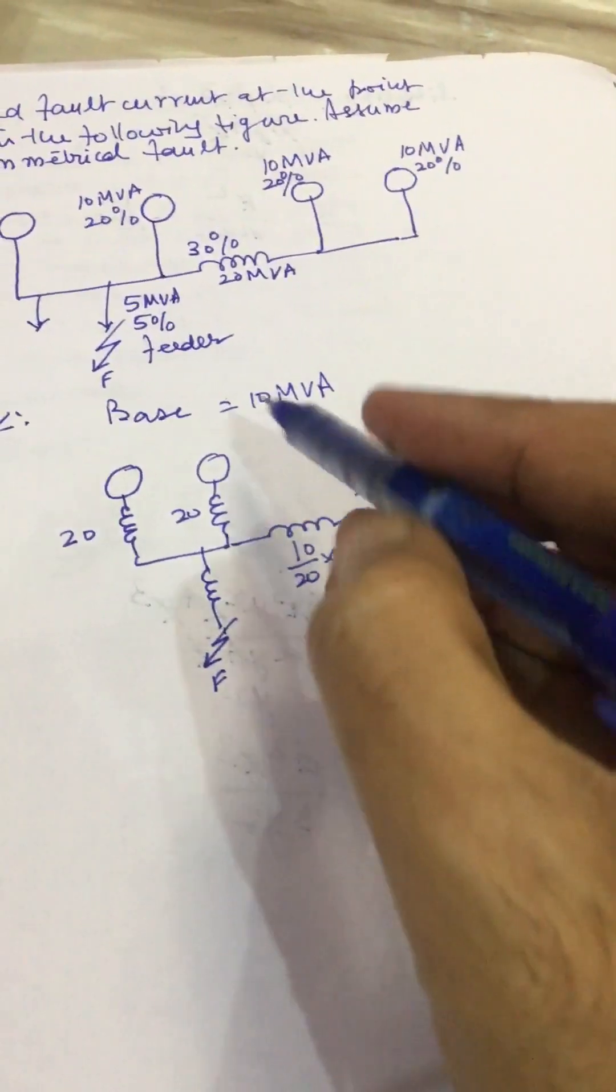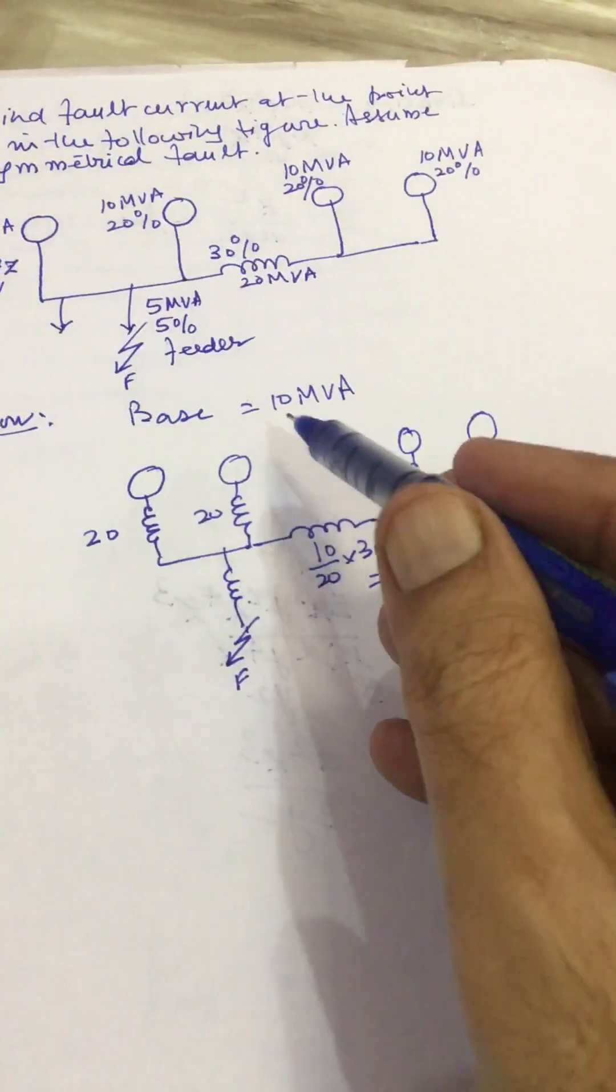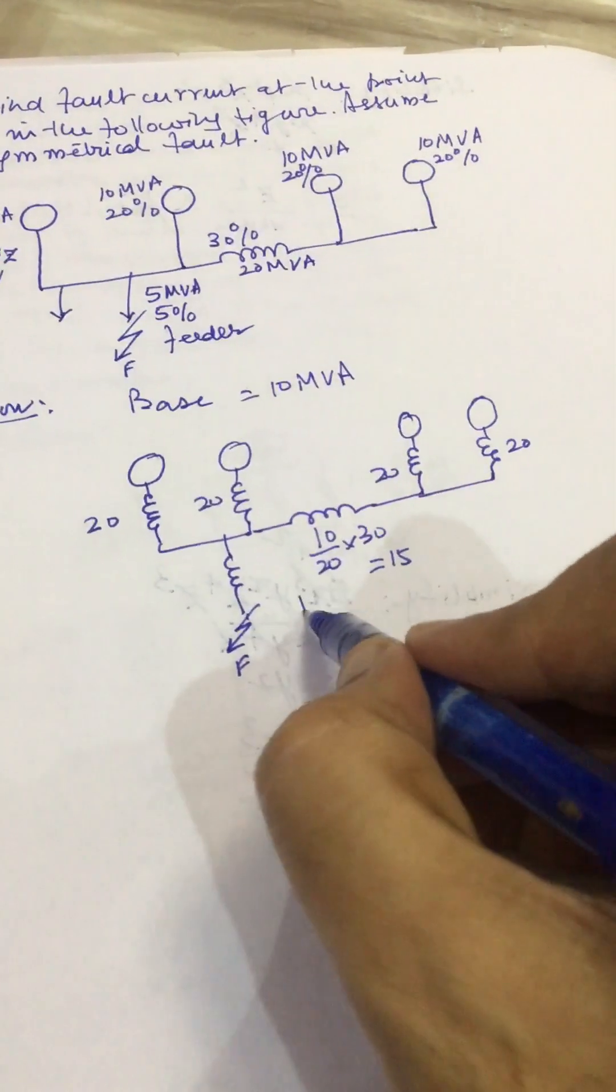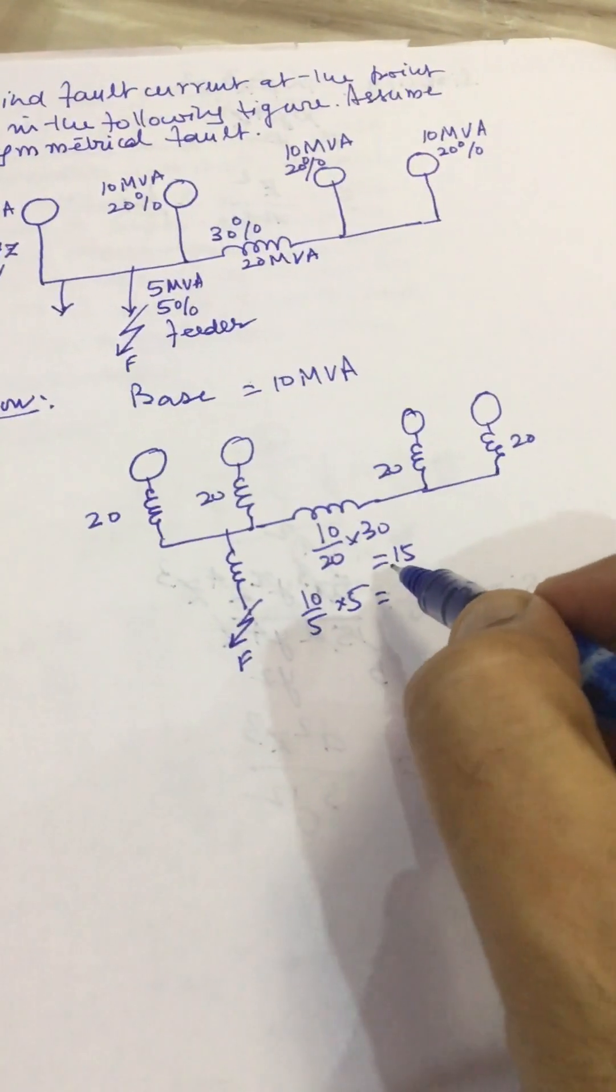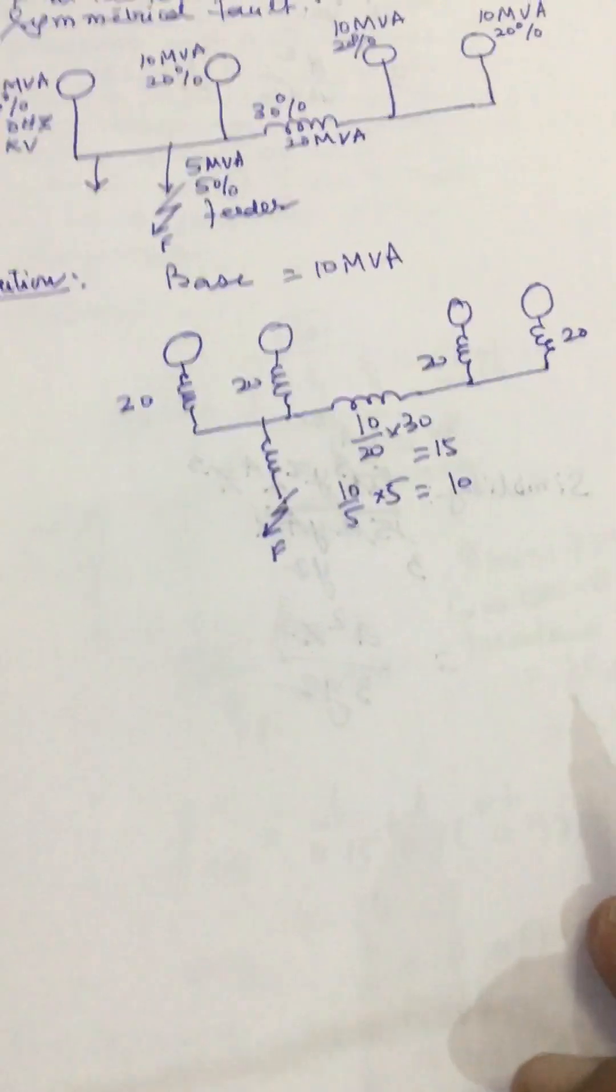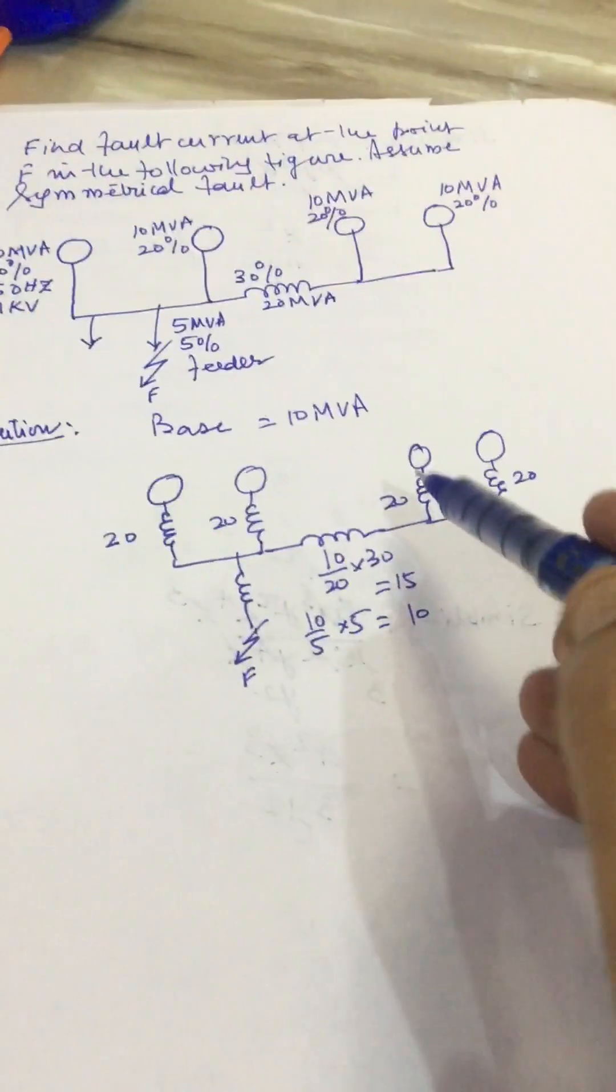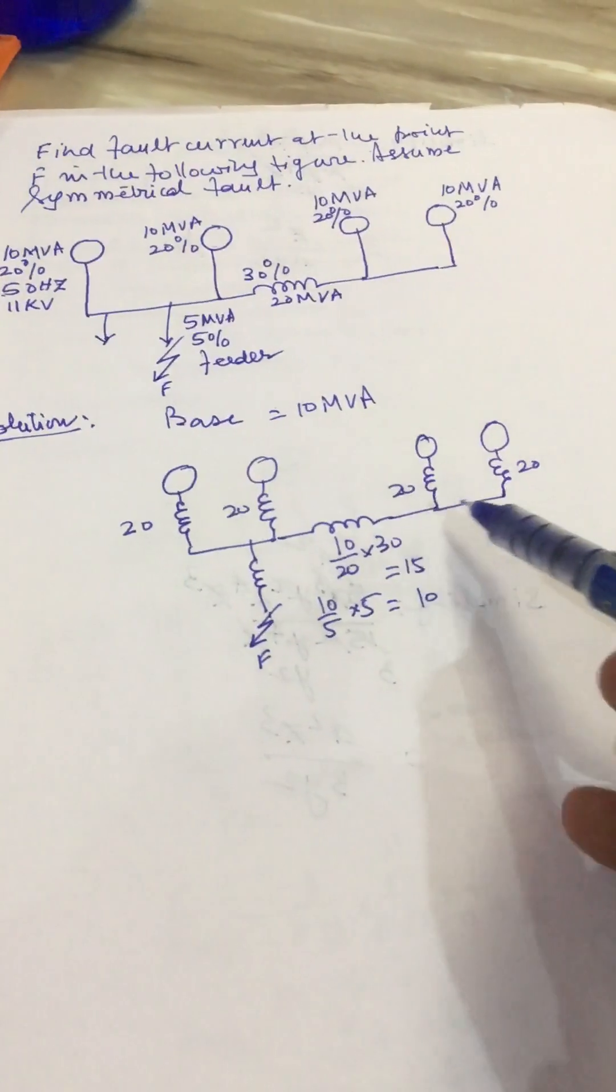This is 5 MVA at 5 percent. So this will be 10 divided by 5 multiplied by 5, so this will be equal to 10 percent. Now we have converted this diagram to reactance diagram.